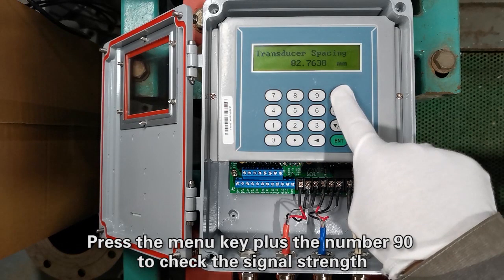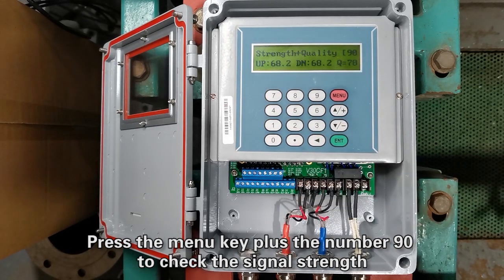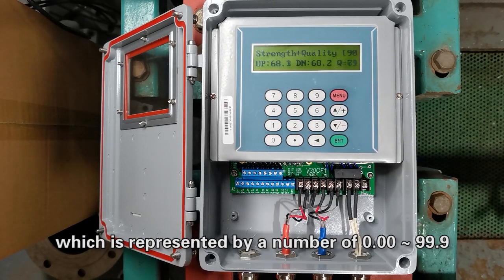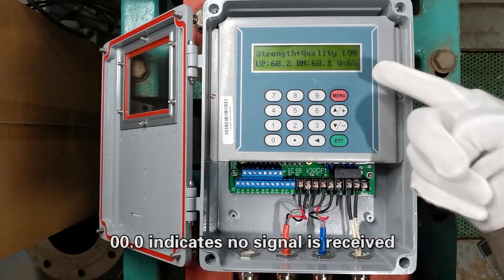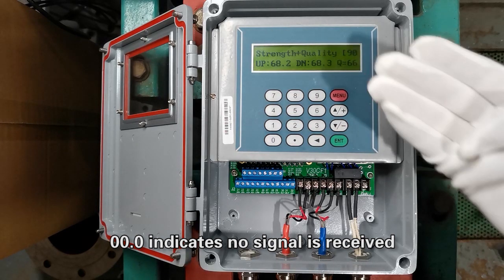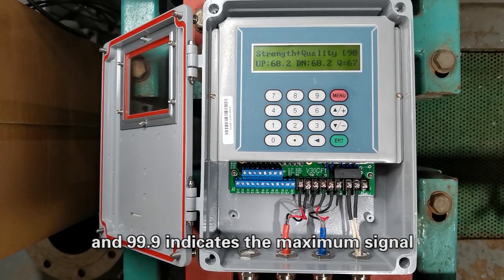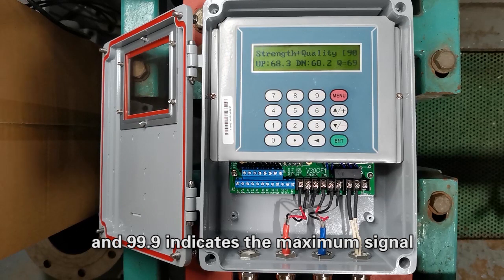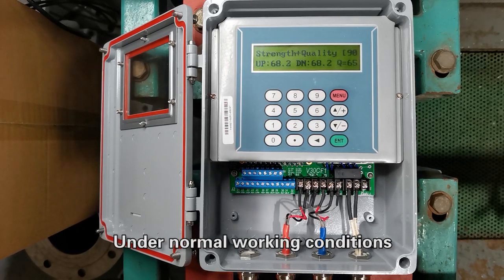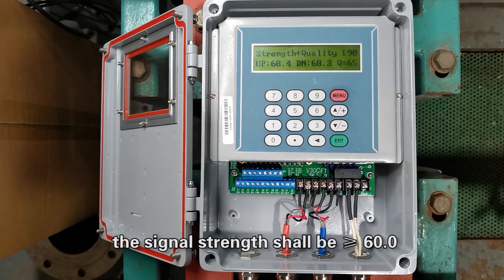Press the menu key plus the number 90 to check the signal strength, which is represented by a number of 0.00 to 99.9. 0.0 indicates no signal is received, and 99.9 indicates the maximum signal. Under normal working conditions, the signal strength shall be more than or equal to 60.0.